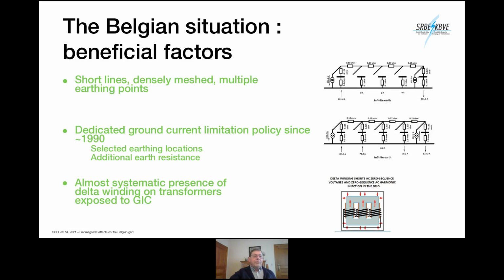And then a third interesting factor in Belgium, that almost all our transformers, which are with a grounded star winding, have also a delta compensation winding. And this delta compensation winding helps to filter out part of the harmonic currents that are generated by these phenomena, which is, of course, interesting to avoid certain resonances, but you cannot avoid all of them, but it reduces. Next slide, please.